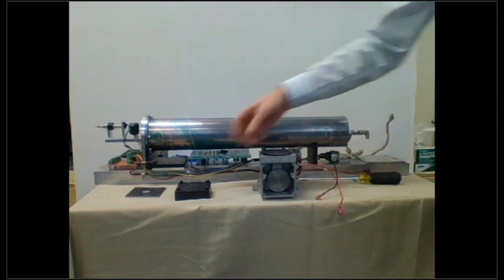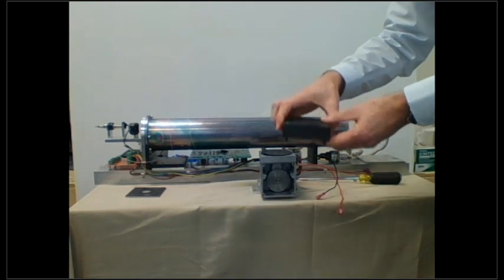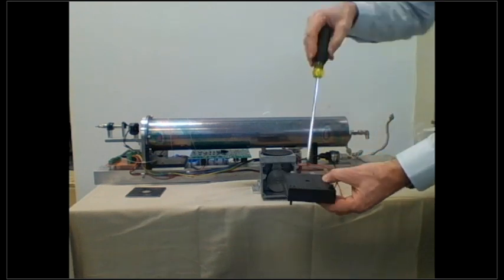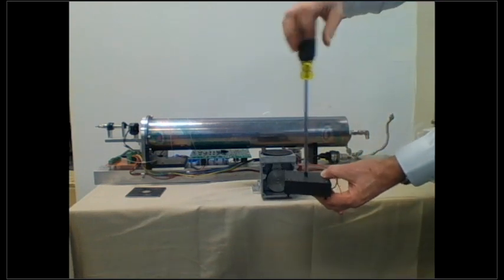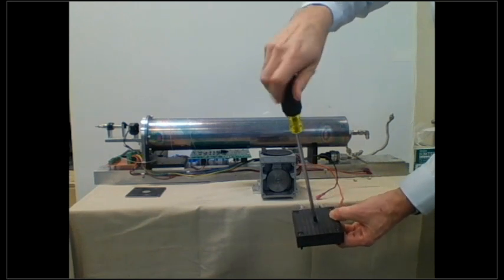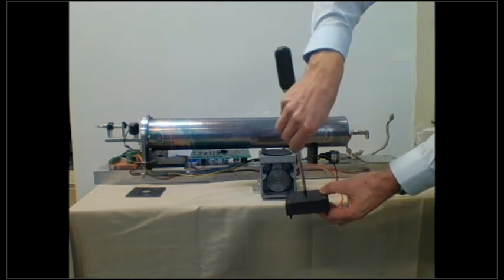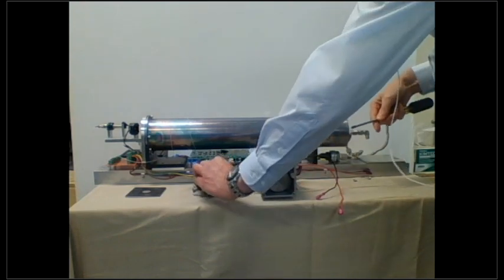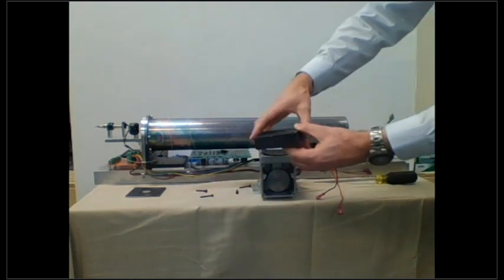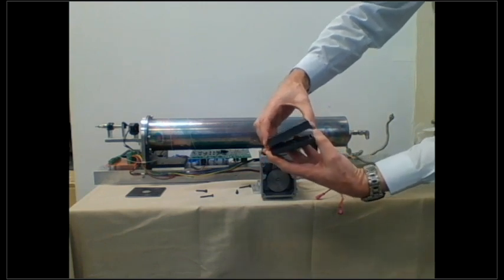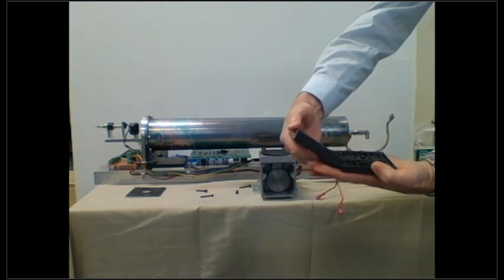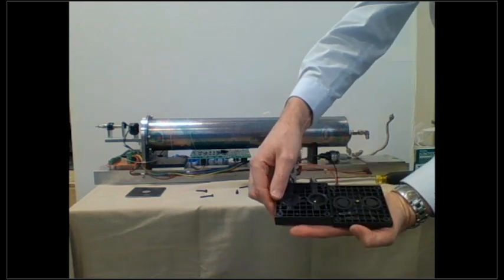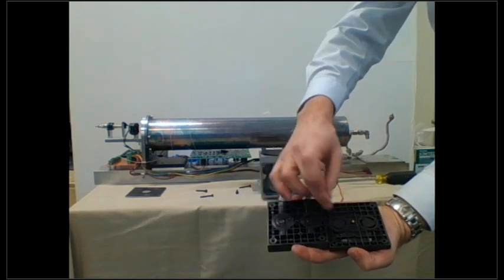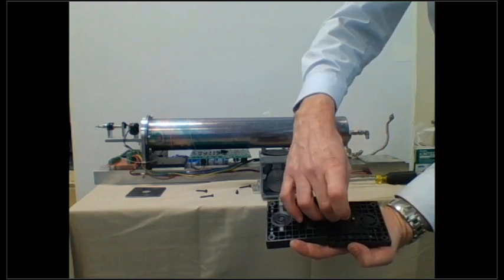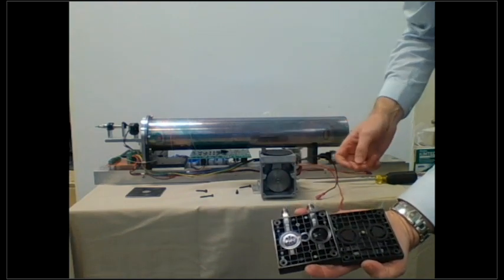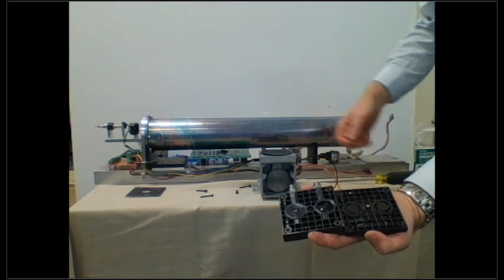There's actually a couple of other items that you need to deal with as well inside the pump head itself. So there's another screw right on the top that you can undo. And the head is actually in two pieces, so you can take it apart like this, drop the screw on the floor. And this gives you access to these two gaskets right here. So these can be replaced at the same time as well. The diaphragm and the two gaskets inside the head come as a kit that you can keep on hand and do that at least on an annual basis.